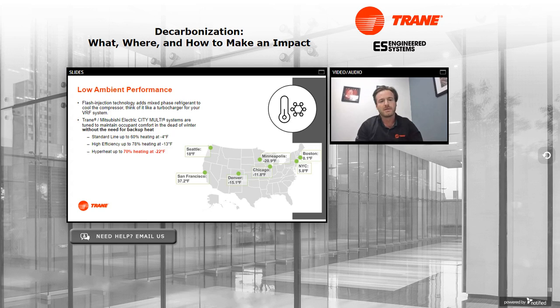On the other side of that coin is low ambient performance. That was a big concern with VRF systems a couple of years ago: am I going to be able to deliver my heat for these cold zones? It gets cold in a lot of parts of the US in the winter, and are we going to be able to actually produce it? And the answer today is yes. There's a new technology that's been introduced to most VRF systems at this point called flash injection technology. What that does is it adds mixed phase refrigerant to your compressor, cooling it down and allowing it to perform better at lower temperatures. You can think of it as like a turbocharger for your VRF system.